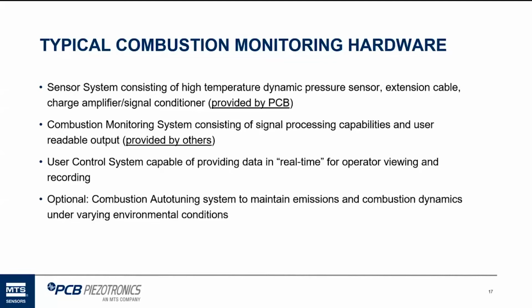There's also sometimes in a plant, most plants will have a control system screen in their operator control room where they can look at data in real time. And it's typically recording, so they can look at trends later on. But the operators will have 14 or 16 squares on a screen, each one showing a combustor, looking at the oscillations in the combustion chamber. And then again, an auto tuning system could be part of a CDMS system.